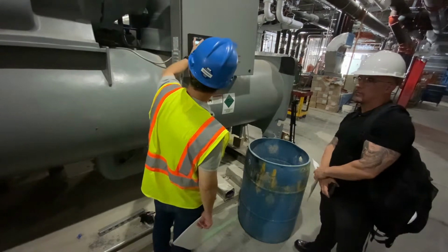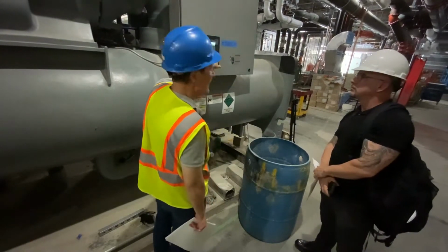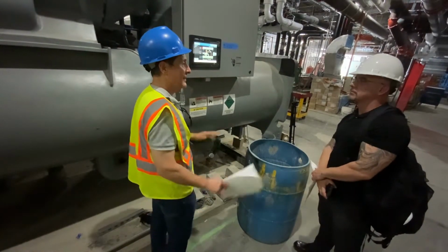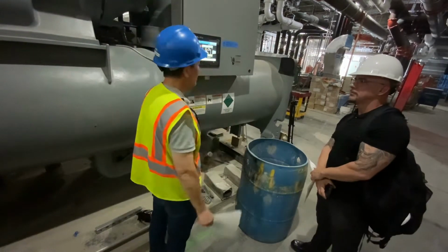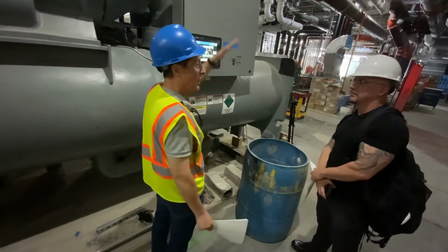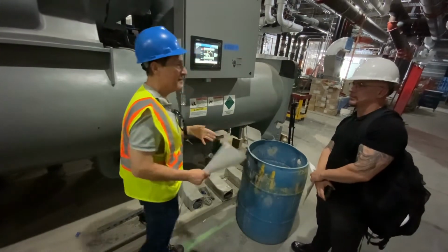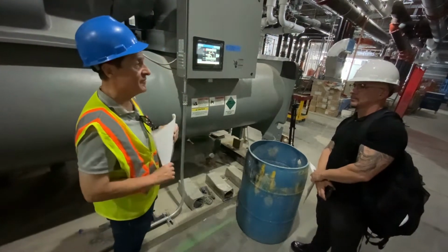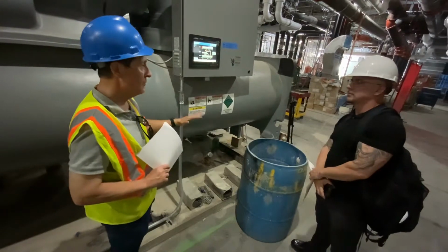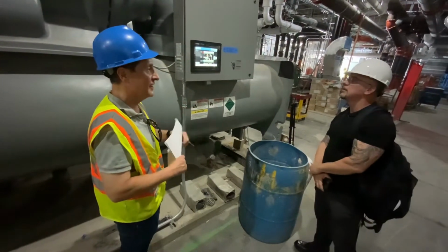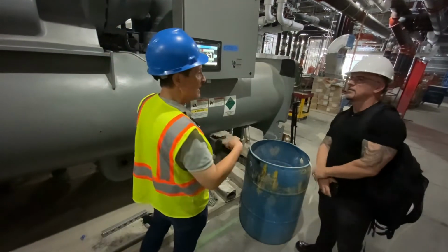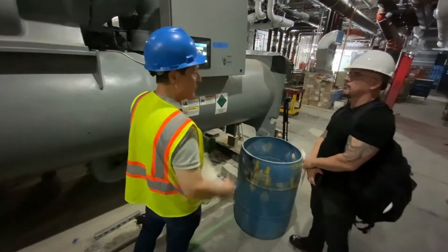So the pressure differential in here is what allows the VFD to slow the speed down, not as much the capacity. So if you had really cold tower water temperature today, that VFD would slow all the way down to its minimum, which by the way, minimum on a centrifugal is about 65%. You go below minimum, you get stall or surge. So the wheel's not turning fast enough to spin the gas up to high enough speed to create compression. So that's why you have a minimum speed.